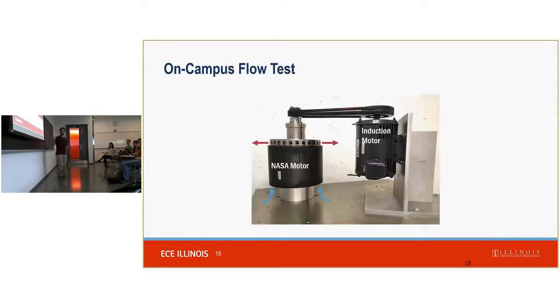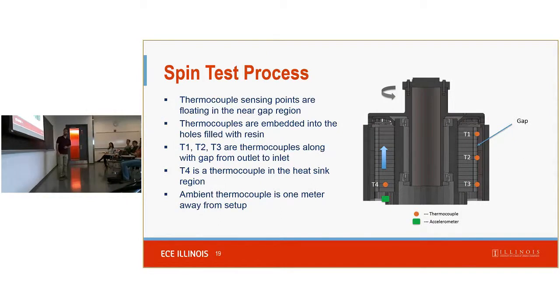So the next category to talk about is cooling and airflow testing. In the same test that we did about a year ago at an off-site location, one of the results was that it looked like we were getting insufficient airflow to cool the motor, and that's really concerning. So we built a test setup on campus to use the same slightly scaled down motor and to drive it with a different motor up to partial speed, and added instrumentation there with thermocouples and pitot tubes to measure the pressures. That gave us a better idea of how much airflow was getting through and how much windage losses, and so the temperature rise associated with that.